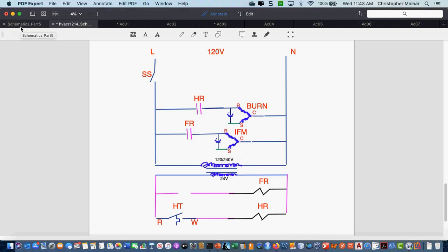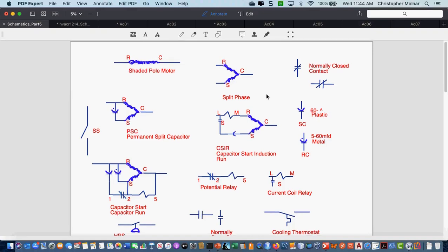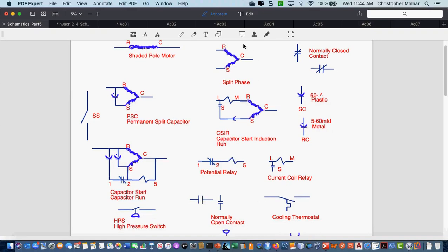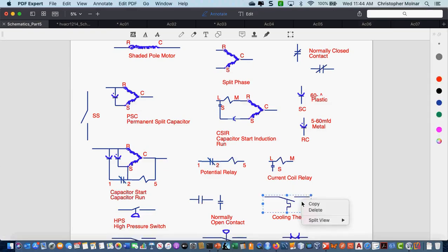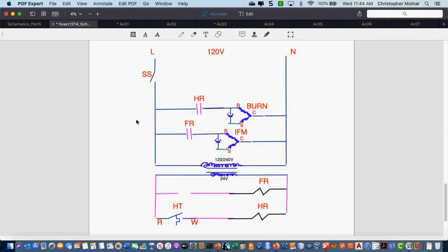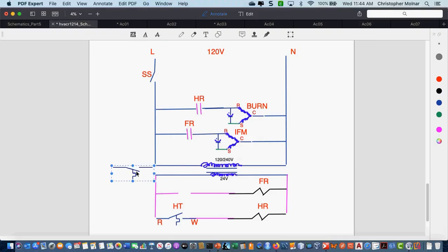Is it going to open on a rise in temperature, or is it going to close on a rise in temperature? It will close on a rise in temperature and blow the hot air and open. That's correct. So what you're going to use here is really a cooling thermostat, but you're just using it because it gives us the ability to close on a rise in temperature.